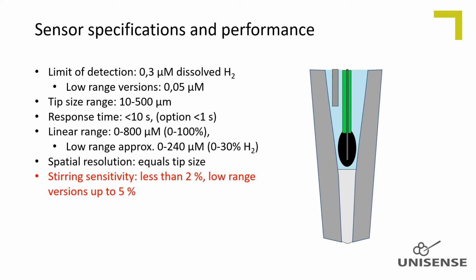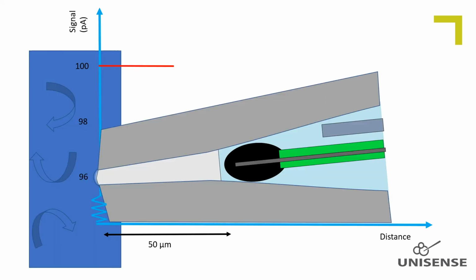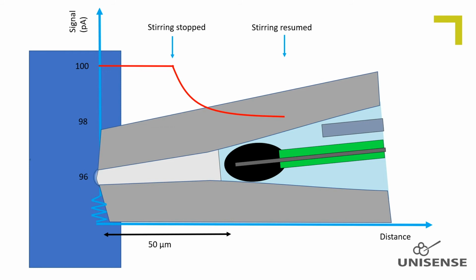For low-range sensors, which can detect hydrogen in the nanomolar range, the sensitivity to stirring could be up to 5%. The sensitivity to stirring is defined as the difference between the signal in stirred and stagnant sample with the same hydrogen concentration. This is exemplified here, where a sensor is measuring in a continuously mixed sample. When the stirring is stopped, the signal decreases about 2%, which is typical for a standard range hydrogen sensor. And when the stirring is reactivated, the signal is back to the original level.